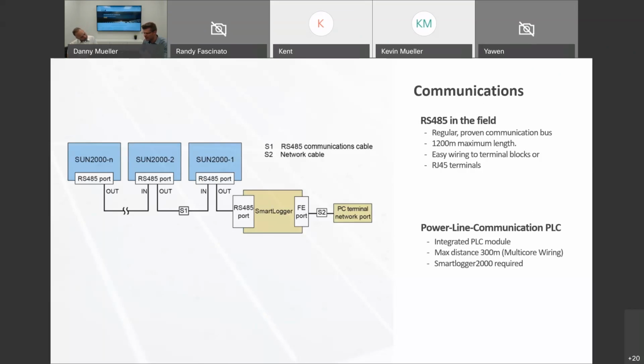When we look into communications, Huawei is a communication company, and they have two typical systems built into the three-phase commercial inverters. The one is one you probably have used already in the past. It's a very proven and reliable old-fashioned RS-485 communication. You daisy chain all the inverters. The inverters are connecting then to the Huawei Smart Logger, which is their communication gateway. And then the communication gateway processes all the data and will forward that data to the Huawei NetEco monitoring server. That's one option when you want to run a wire.